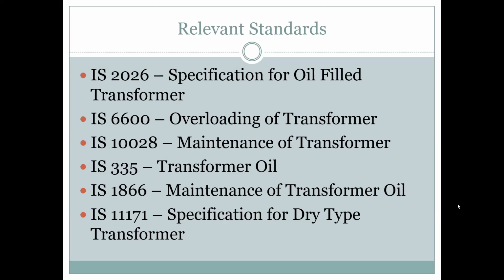So in case of overloading, we also have some load sharing. Other transformers are kept in standby by the load sharing method, so they can distribute the load. Overloading a transformer on a continuous basis is not allowed. It will ultimately ruin the transformer. Basically, you over-design the transformer. If I design 10 MVA and declare it as 8 MVA, that is a different issue. But if I design a 10 MVA, it is not allowed to take even 11 MVA. But if, for emergency purposes, I have to load it instantaneously sometimes, again you have to underload it during the 24 hours of operation, at 90%, 80%, to recover the life of the insulation.